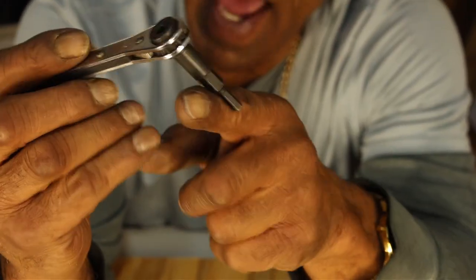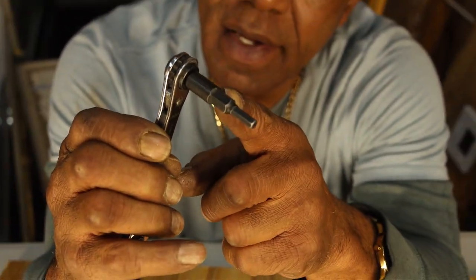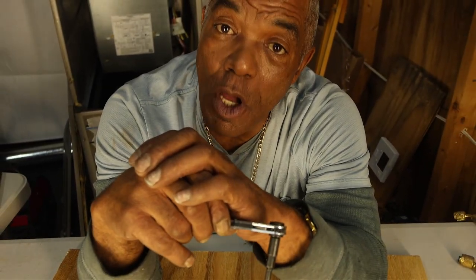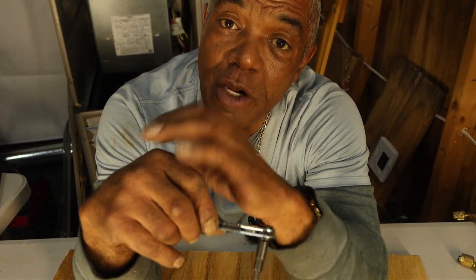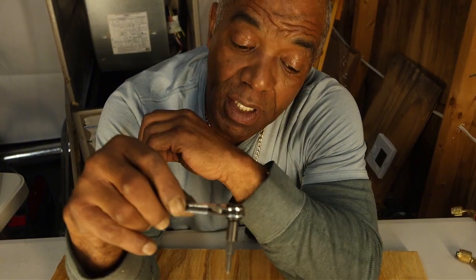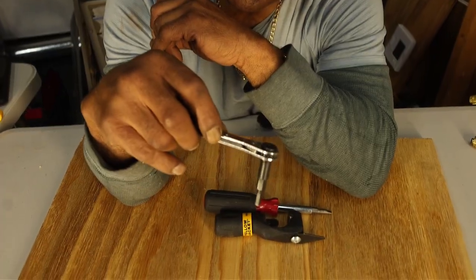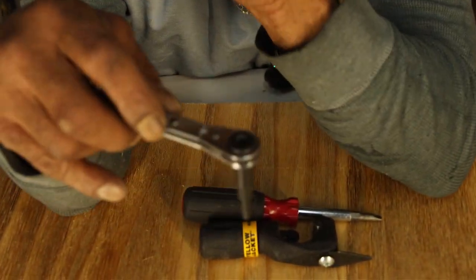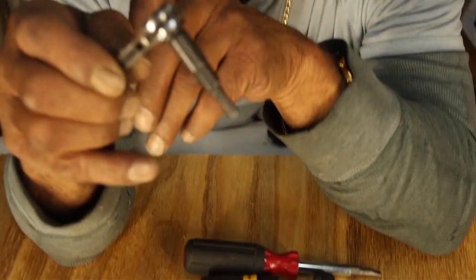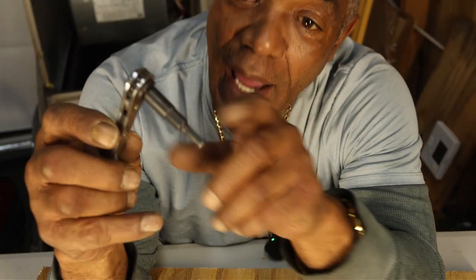The larger Allen key further back would be used on the suction side, which is the low side, which is the thicker of the two coppers, which is the insulated copper. That is my low side. That feeds my evaporator coil. The high side, which is the red, which is the thinner copper, it's non-insulated. That is my liquid side, and that feeds my outdoor condenser.